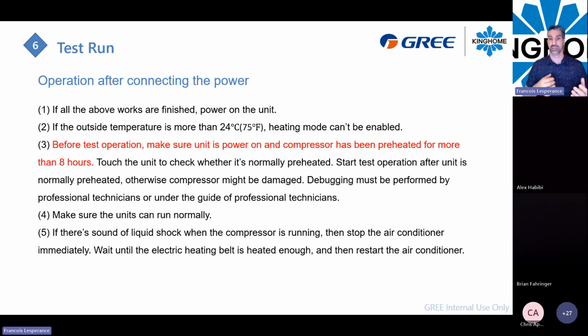The factory will say it needs to be powered and preheated for 8 hours. Well, it depends on the temperature of the compressor. If you put your finger around the compressor and you feel it warm, you're good to go. If it's 30 degrees outside, you don't have to wait any more minutes to start the unit.